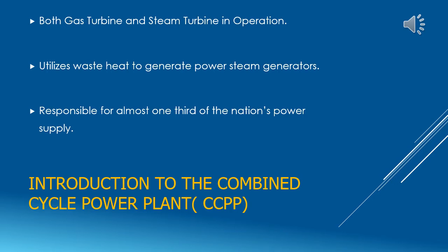What is the combined cycle power plant? It uses both the gas and steam turbine to produce up to 50% more electricity from the same fuel than a traditional simple cycle plant. The waste heat from the gas turbine is routed to the nearby steam turbine, which generates the extra power. The role of a combined cycle in a country is crucial as it is responsible for almost 1/3 of the nation's power supply.